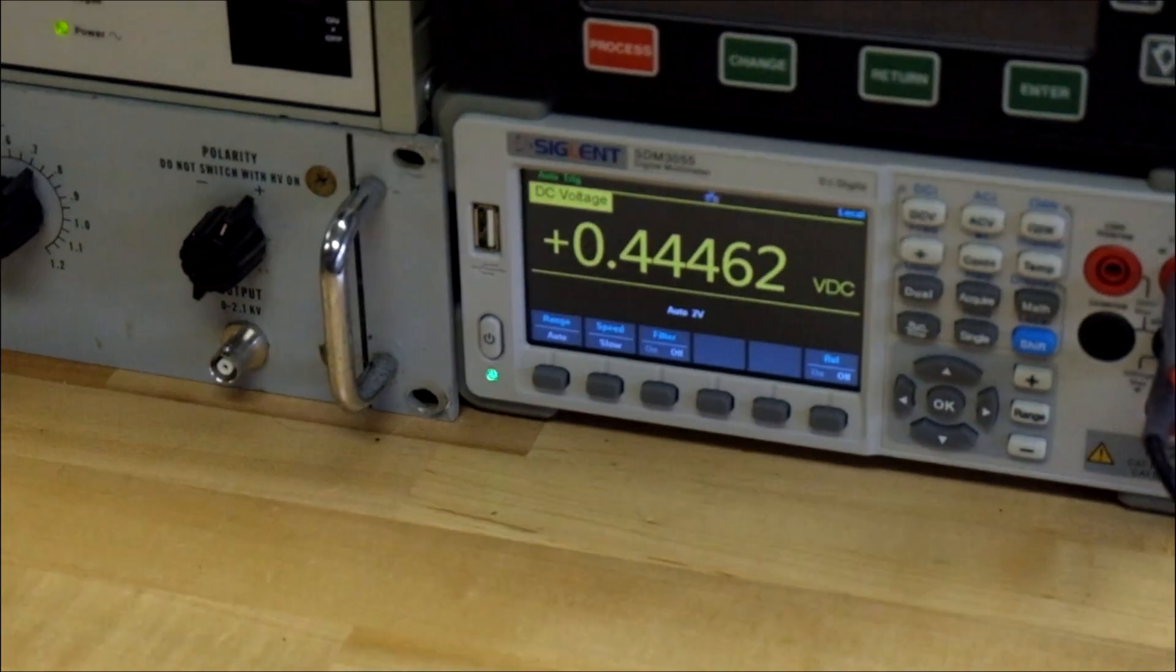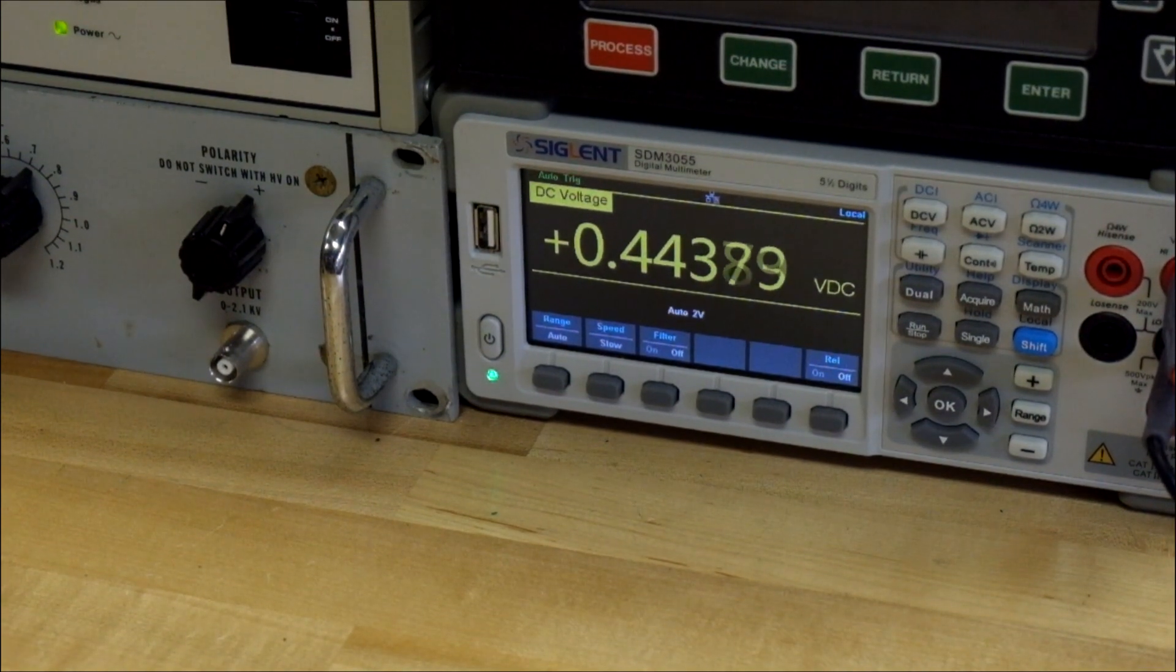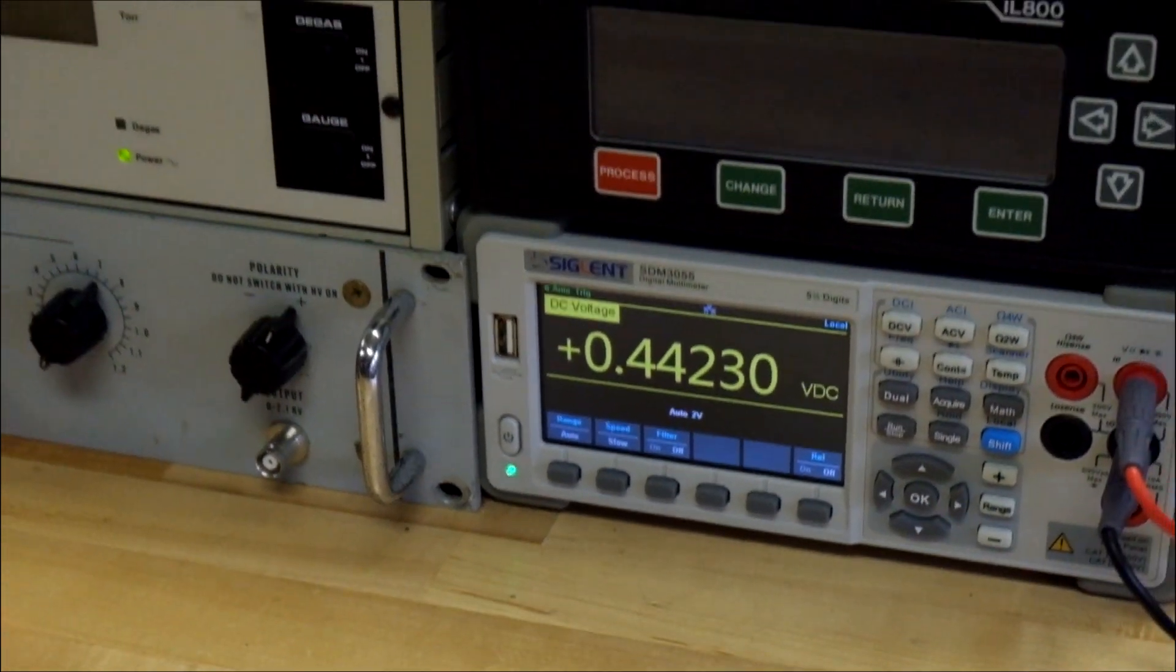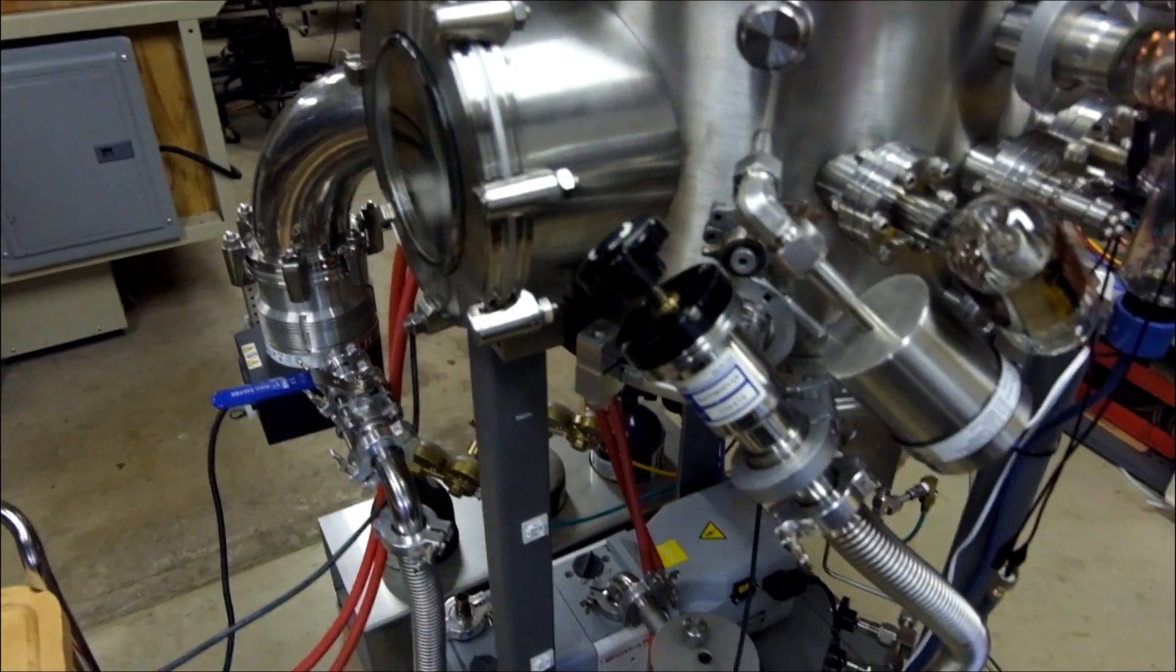We're at about 44 millitorr, so I'm going to turn the turbo pump on in a minute here, and that's going to start dropping a lot faster. You'll notice the pump got a lot quieter, it does this as it goes.